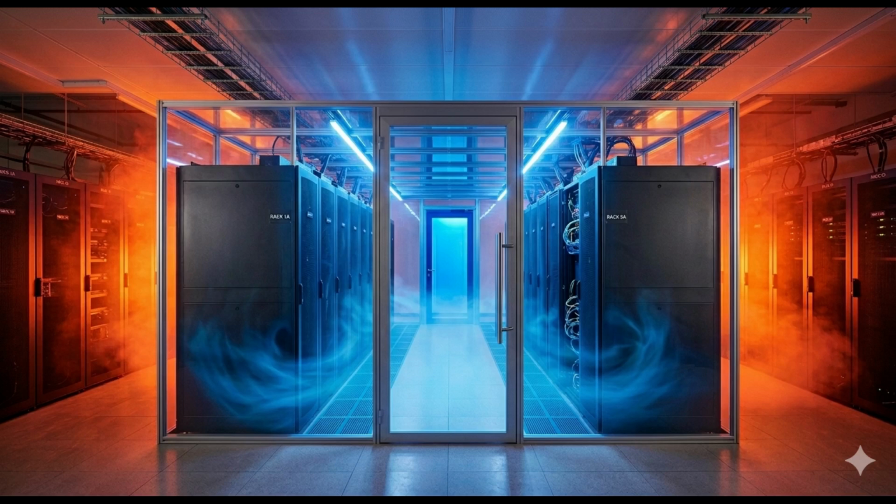Start at the evaporator. So the evaporator is the heat exchanger located inside the computer room, usually an in-row or a side cooler unit sitting right next to the racks. The refrigerant enters this coil as a low-pressure mixture of liquid and vapor. And the hot air from the servers blows across that coil. Yes. The hot return air transfers its thermal energy to the refrigerant. This causes the liquid refrigerant to boil, to evaporate. It absorbs the latent heat.